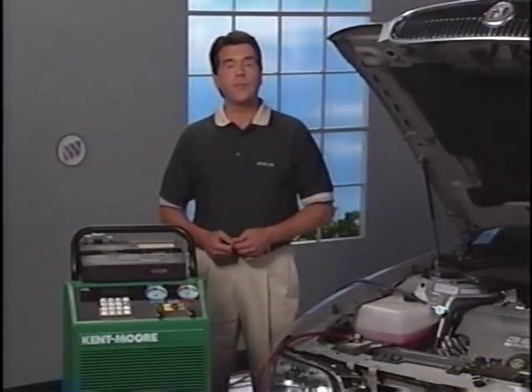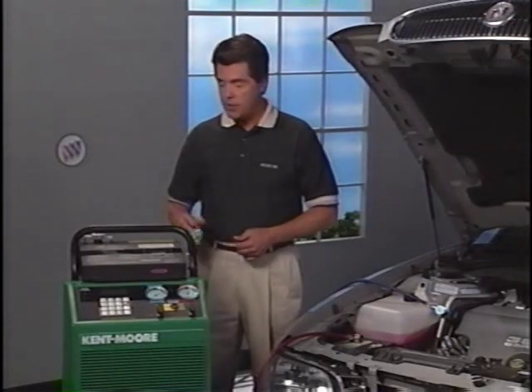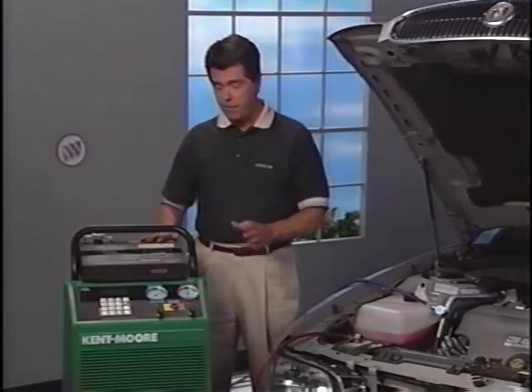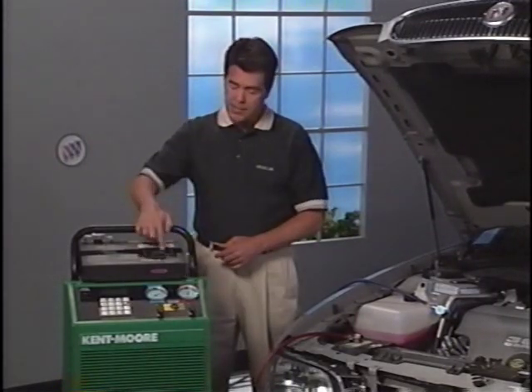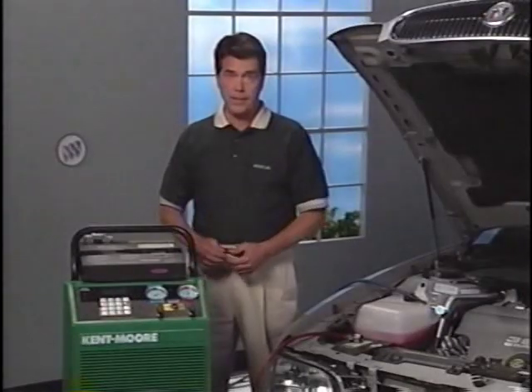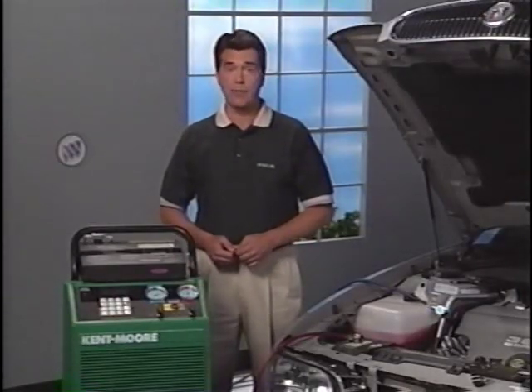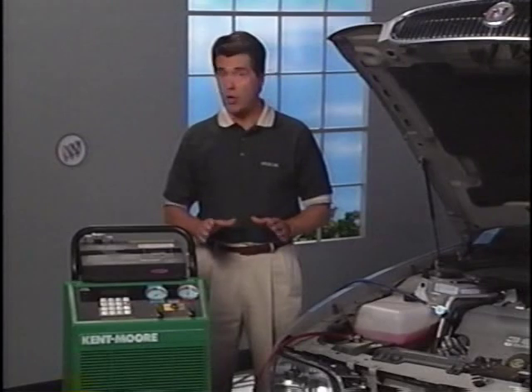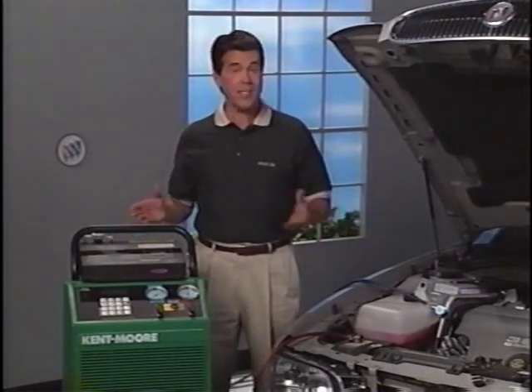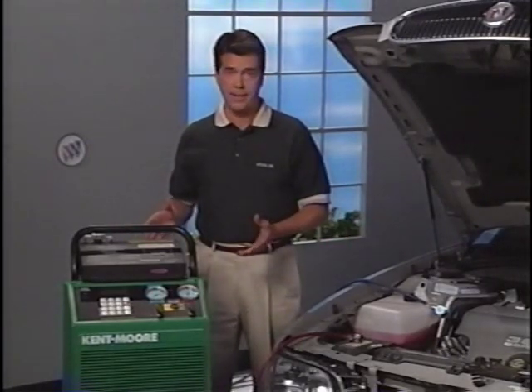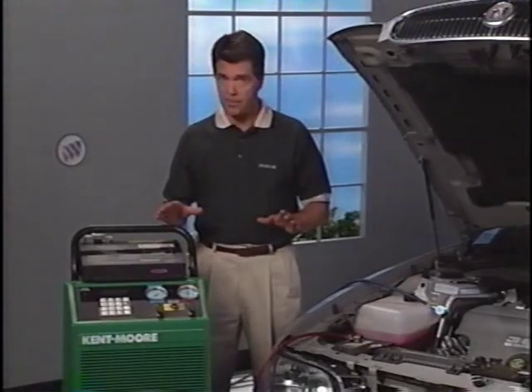There have been reports of incidences when the PureGuard 2 has been removed from the ACR4 because the red excess air light remains illuminated. The light indicates high levels of air are detected in the refrigerant storage tank. The warning does not interfere with the operation of the ACR4. The pressure caused by high levels of air in the storage tank may slow down or in some cases stop the recovery process. This is not due to the warning system.